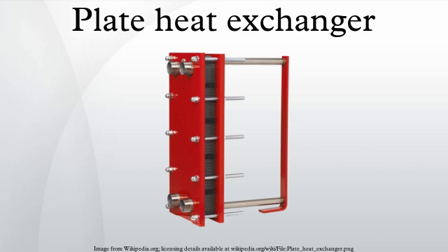A plate heat exchanger is a type of heat exchanger that uses metal plates to transfer heat between two fluids. This is a major advantage over a conventional heat exchanger in that the fluids are exposed to a much larger surface area because the fluids spread out over the plates. This facilitates the transfer of heat, and greatly increases the speed of the temperature change.